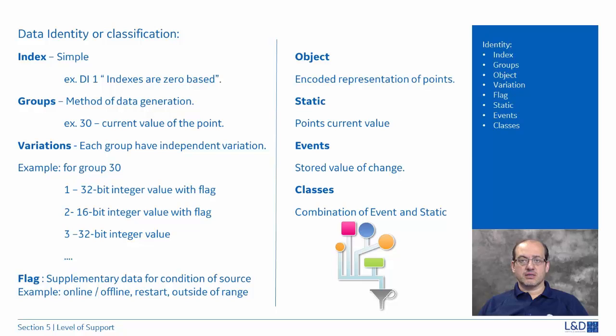The status of breaker 1 is referred to as DI1, right? Digital input 2 would refer to another status, maybe of the same breaker or a different breaker. But what we end up with is a grid of information that basically points out an index to every piece of data or information coming from the field. It is built into this grid of information that is transmitted from the primary devices in the field to the secondary devices in the field, all the way until it reaches the control centers as information transmitted over DNP.